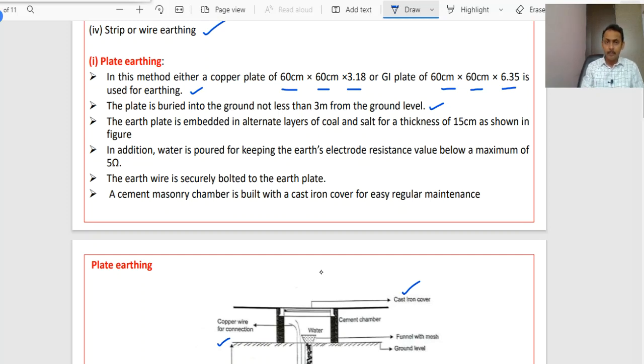Now this earth plate will be embedded in alternate layers of coal and salt for a thickness of 15 centimeters, as I told you earlier. In addition, water will be poured in this arrangement in order to bring the electrode resistance value below 5 ohms. Because of that, the resistance gets reduced. After making all these arrangements, the earth wire is securely bolted to the earth plate, and you enclose it in a cement chamber. At last, you cover it with a cast iron cover for easy and regular maintenance.